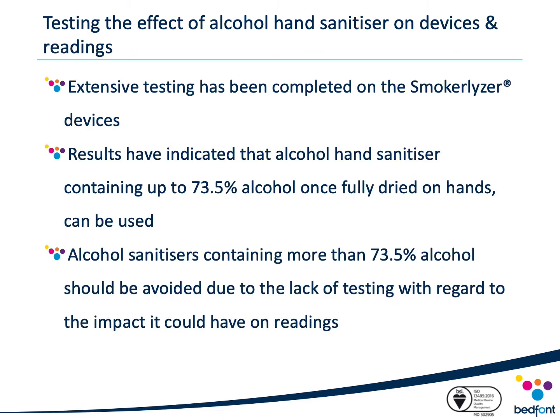Due to an ever-increasing need for healthcare professionals to use alcohol hand sanitisers in response to COVID, extensive testing was performed by Bedfont to determine the effect hand sanitiser had on Smokerlyzer devices. Results indicated that alcohol hand sanitiser containing up to 73.5% alcohol, once fully dried on hands, can be used. However, hand sanitisers containing more than 73.5% alcohol should be avoided due to the lack of testing regarding the impact it could have on CO readings.